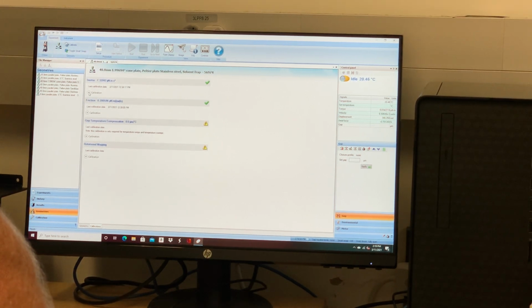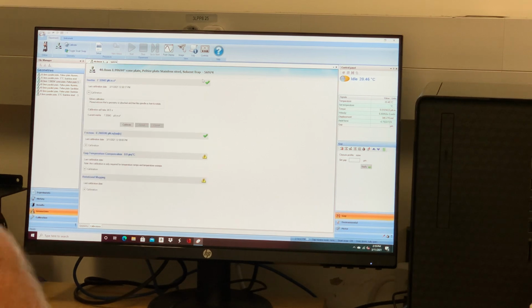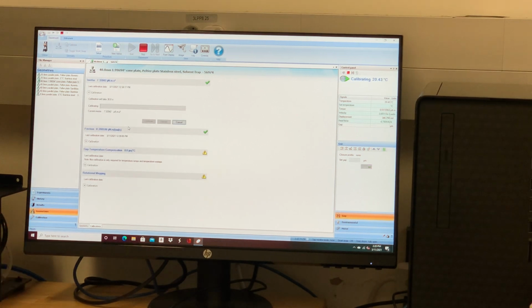And the first one here is the geometry inertia calibration. It's basically doing the same thing, and it gives you instructions too. It says, please ensure that a geometry is attached and the spindle is free to rotate. Okay, the geometry is attached, and we hit calibrate. So another 30-second calibration. It's doing the same thing as the instrument inertia calibration. It's just going to get a number for the geometry, and it's going to combine those.